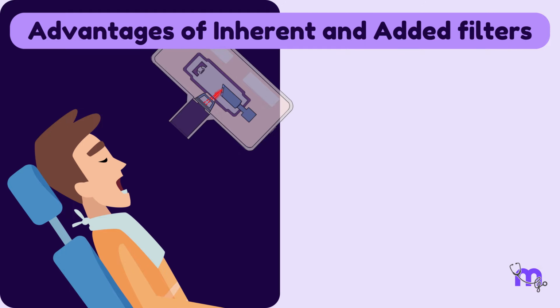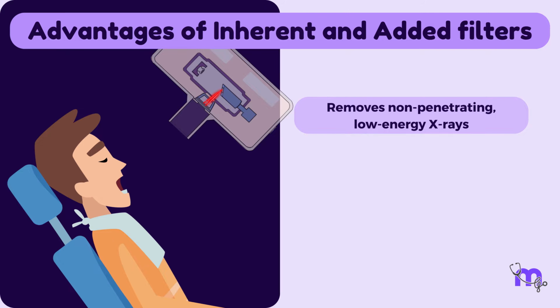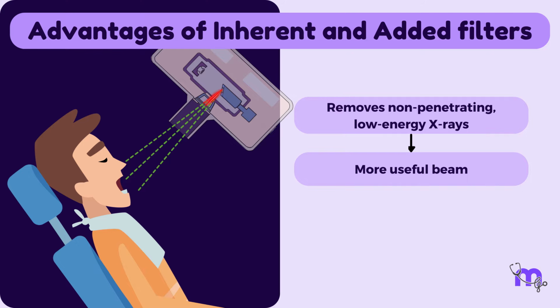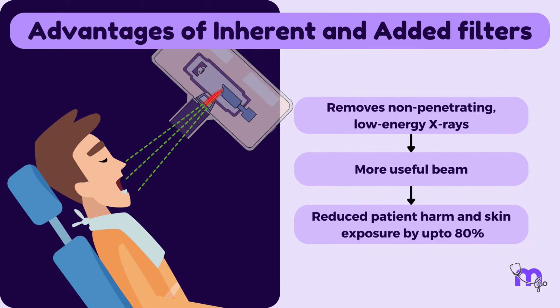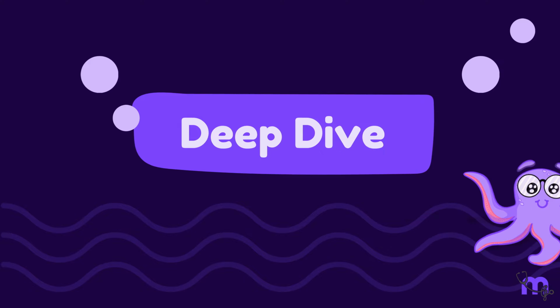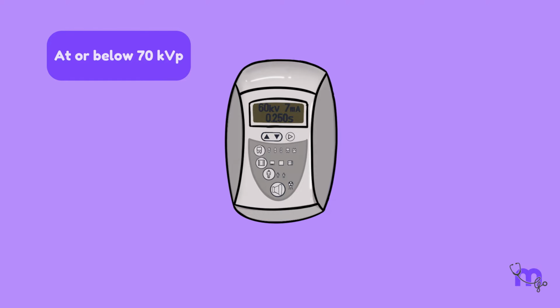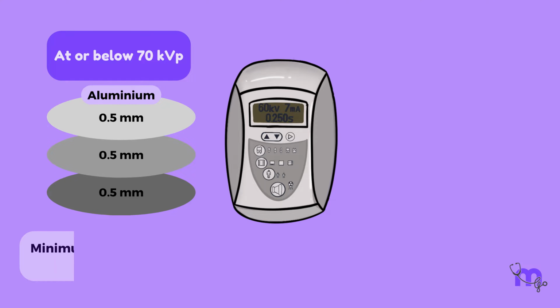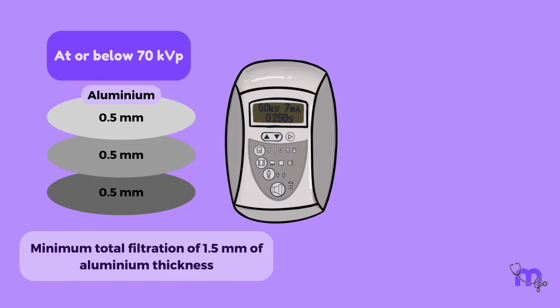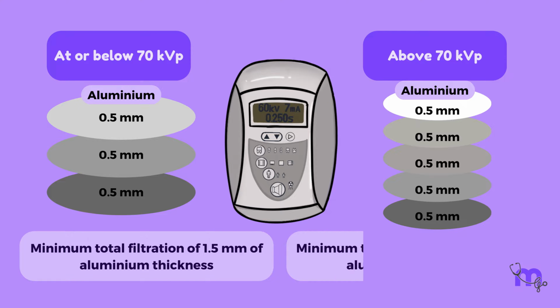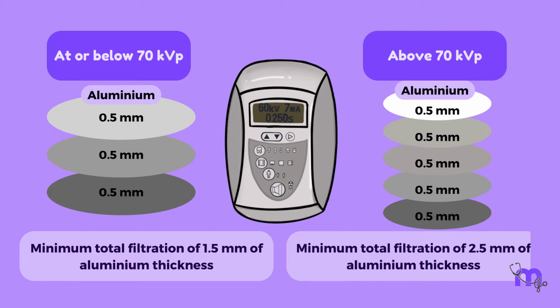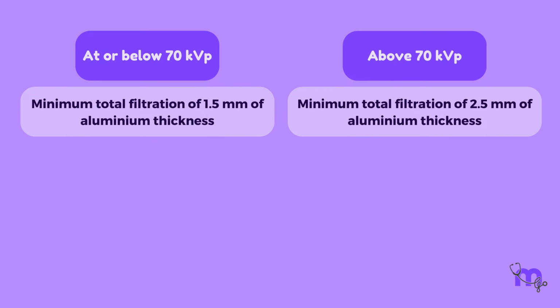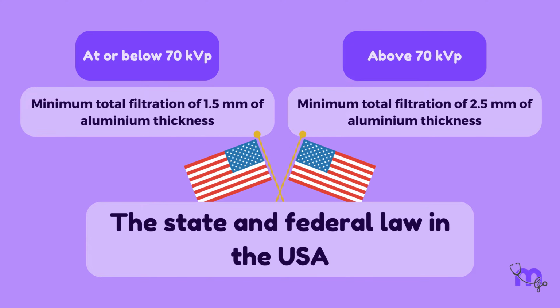Both inherent and added filters remove non-penetrating low-energy X-rays, resulting in a higher energy, more useful beam that reduces patient harm and skin exposure dose by up to 80%. Dental machines operating at or below 70 kVp require a minimum total filtration of 1.5 mm of aluminium thickness. Above 70 kVp requires a minimum total filtration of 2.5 mm of aluminium thickness. These values are regulated by the state and federal law in the USA.